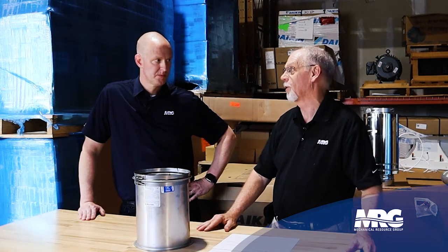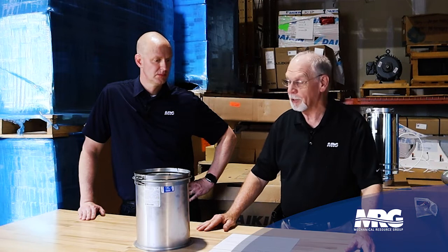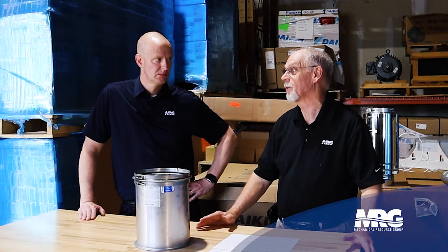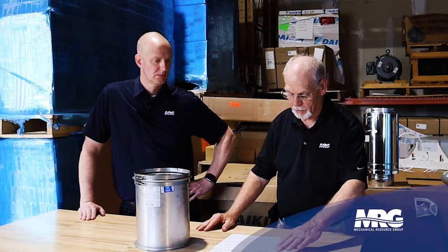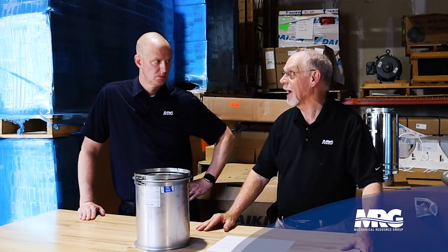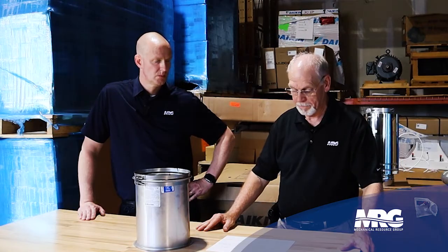The Category 3 is classified as a non-condensing boiler because of the temperature of your water, but it could condense if they change the water temperature. And then on your Category 4, it is your positive with the condensing factor in it, because it's usually low temp. They have come out with some new plastic materials for the condensing boilers. That is not the PVC, it's a polypropylene. Okay. And it is designed for that, and that's a new product that's out now.